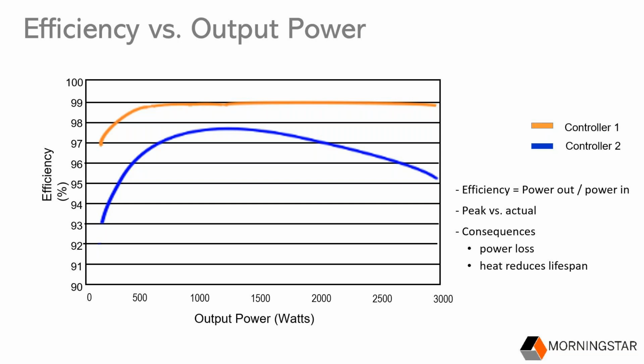Other MPPT brands have been shown to have more than 2 times the energy losses at higher output power levels. So when a manufacturer quotes you a conversion efficiency for a controller, you need to know the output power at which that efficiency was calculated and how much that efficiency will vary at higher output power levels. In a grid-tied system, a 0.25% difference in efficiency is a big deal, and here we're talking about 1 to 3%.